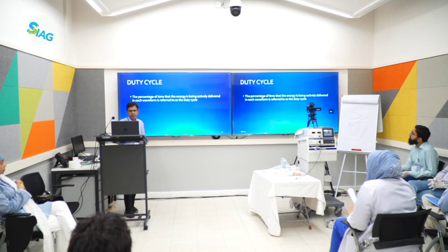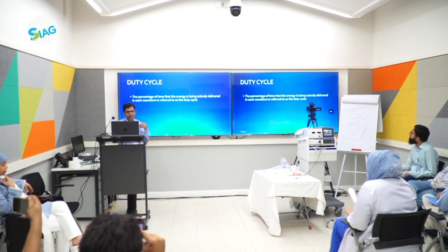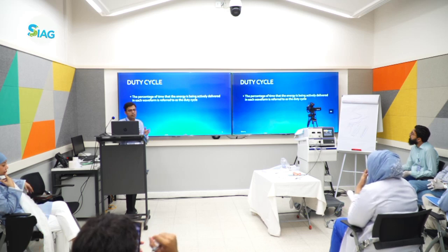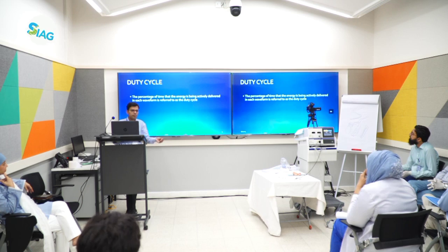What is duty cycle? Might sound a bit boring, but it's again very important, because this actually means the time the current flows uninterruptedly, right? If we define it, it's the percentage of time that the energy is being actively delivered in each waveform, be it cutting technique or coagulating technique. In simple terms, is the current flowing uninterruptedly, or are there some interruptions in between? We will see how it defines the diathermy.